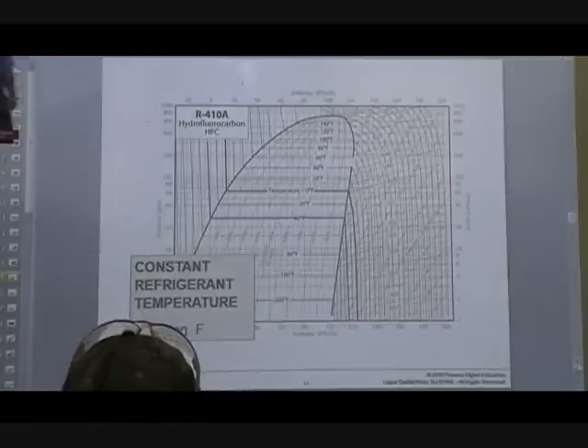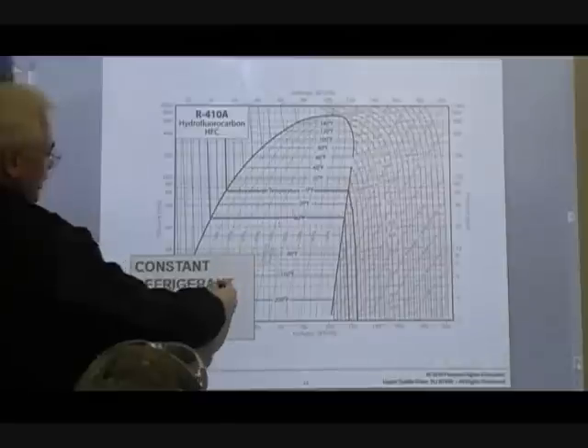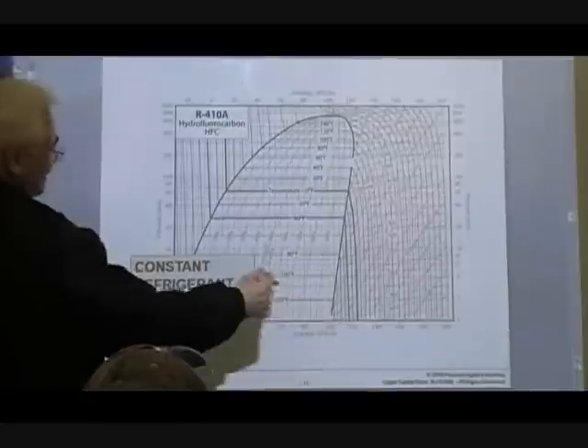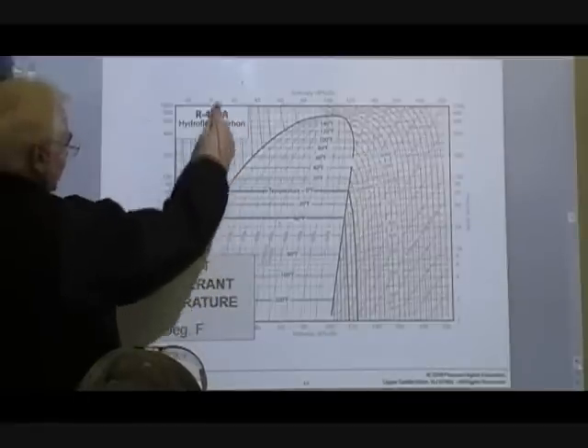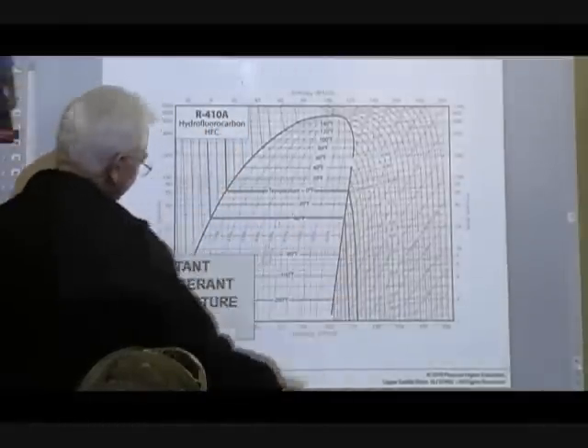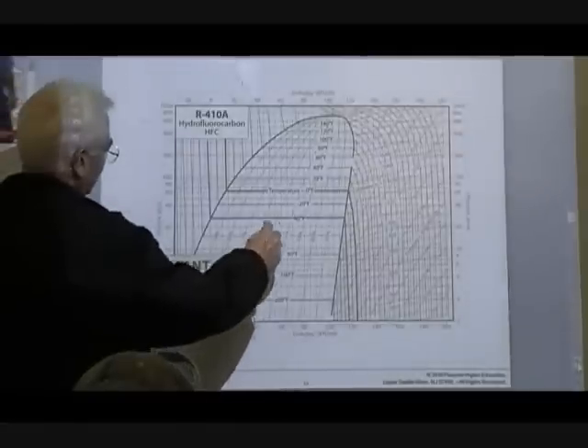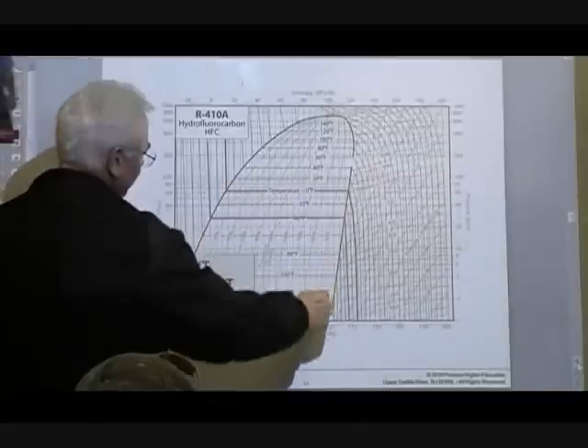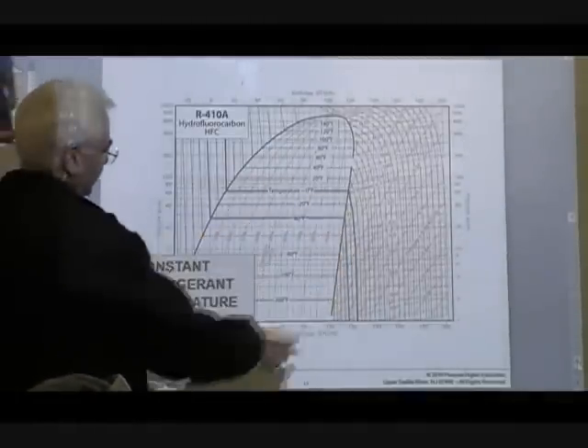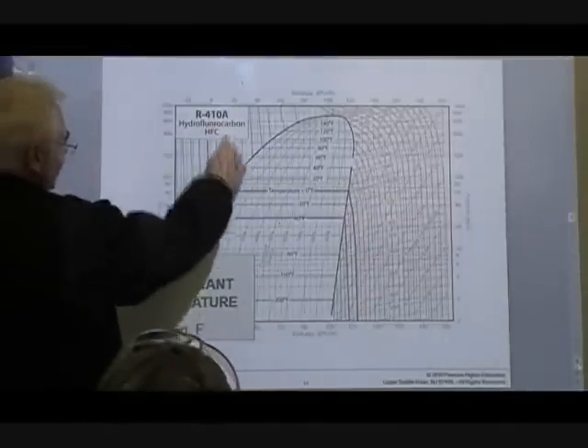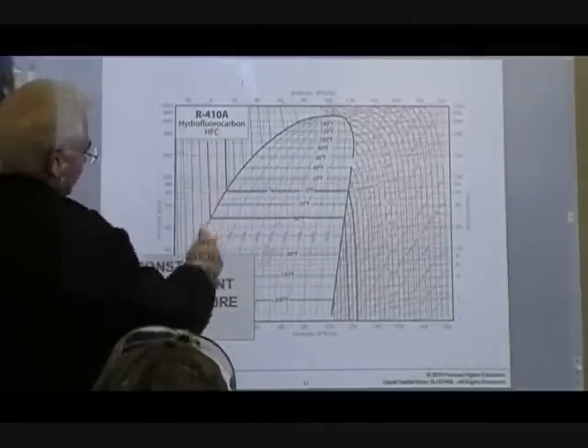Outside of the saturation curve, your pressures are going up and down and your refrigerant is going through the various phases of change. When you get outside of the bell curve, the temperature lines change direction — the temperature goes up instead of vertical. The most important part is what's happening inside the curve, from saturated liquid to saturated vapor. That's where the work is being done — in your condenser and in your evaporator. Outside the saturation curve, the temperature lines change.